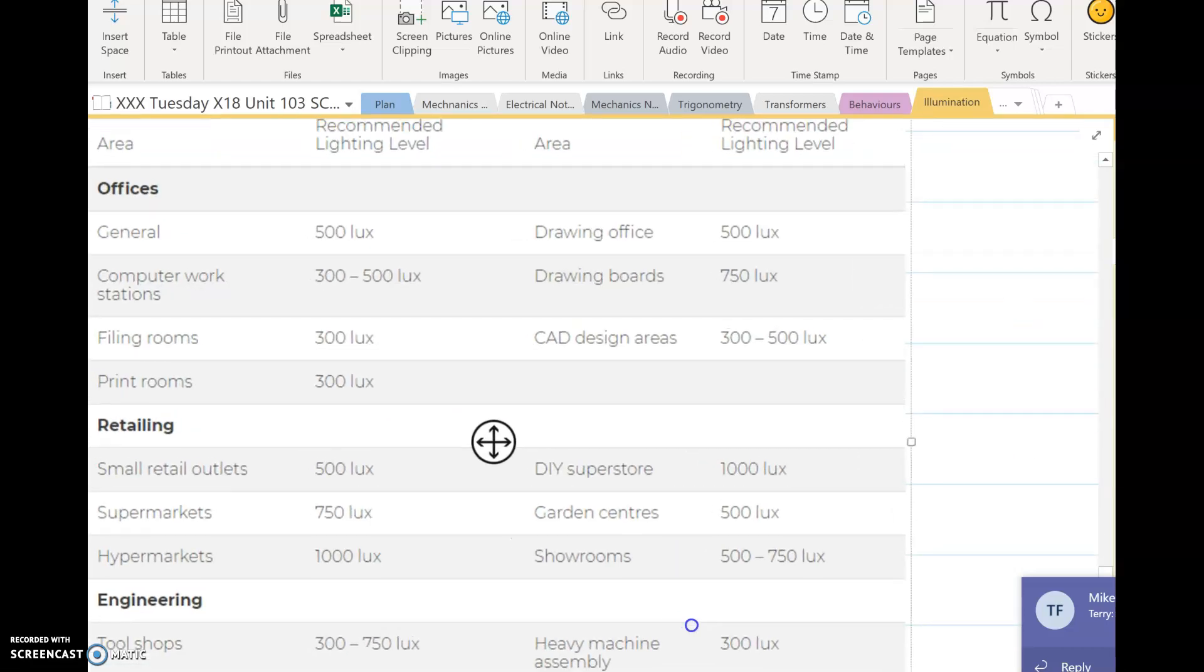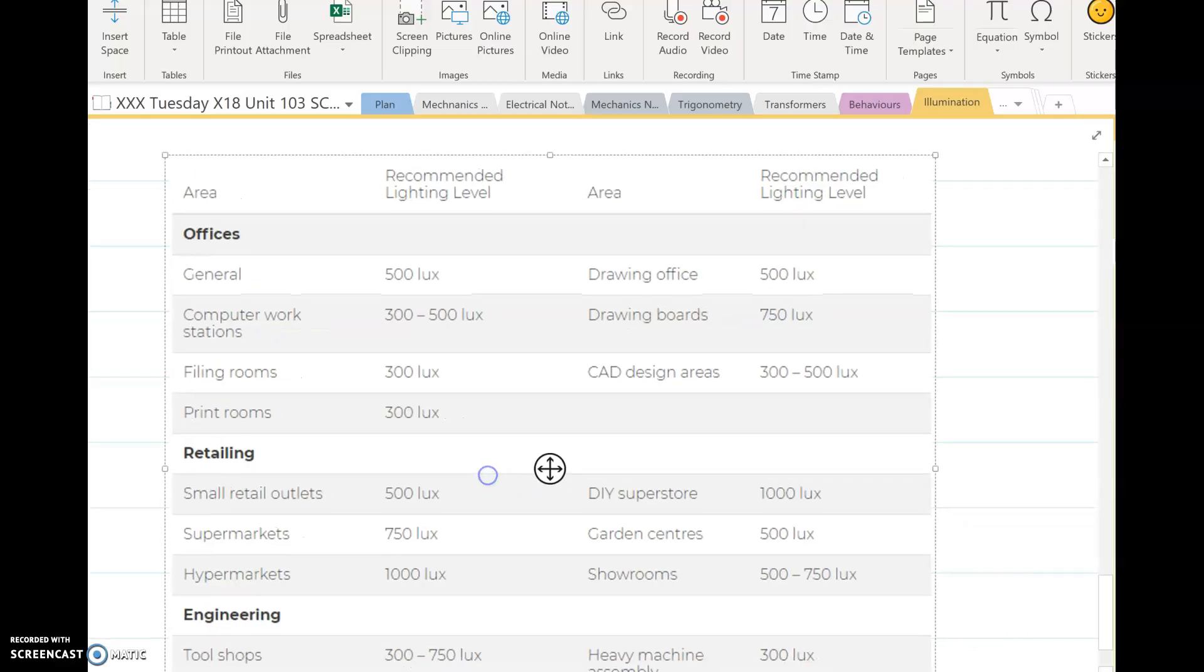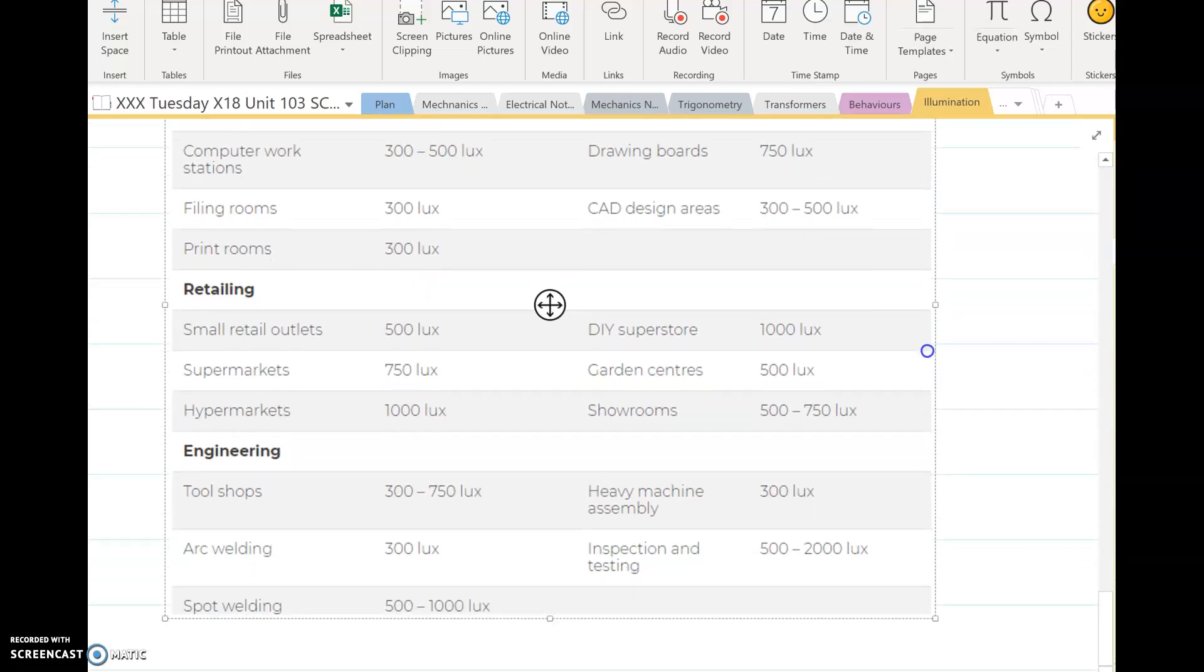Basically, if we look at the recommended light levels, for CIBSE, the Chartered Institute of Building Service Engineers guides, they say the following levels. Offices, general work areas, 500 lux. Drawing boards, 750 lux, so it depends on the activity that's going on. If it's a computer room, like offices, workstations, it's quite a low lux area because you don't want a lot of glare off the lights, because people are tuned into the monitors.